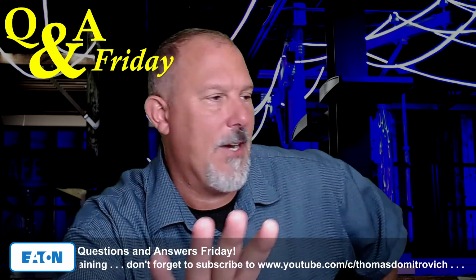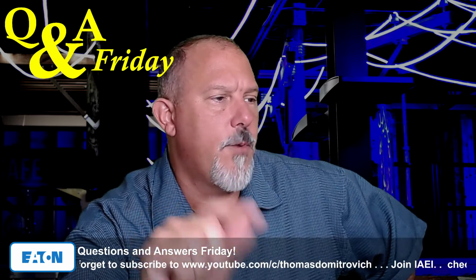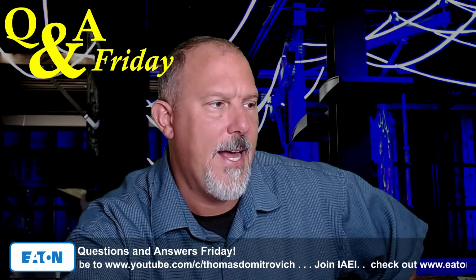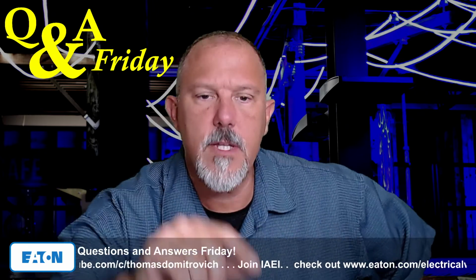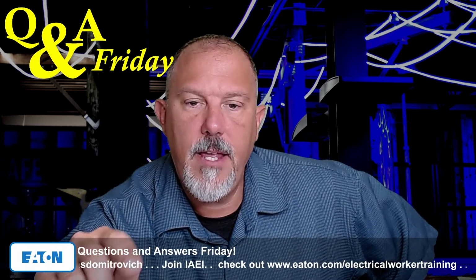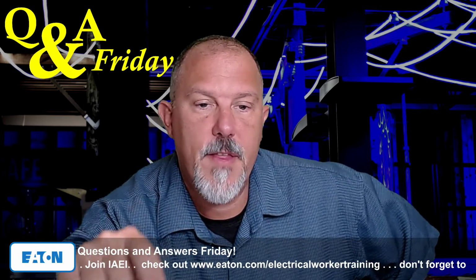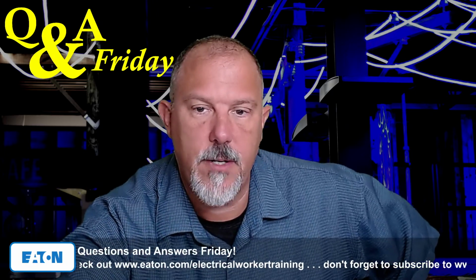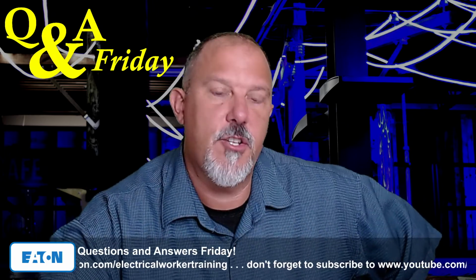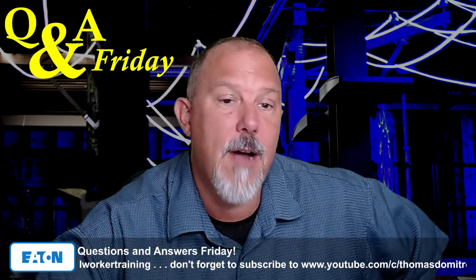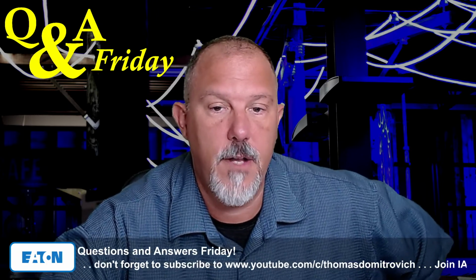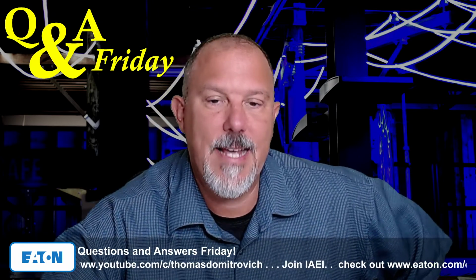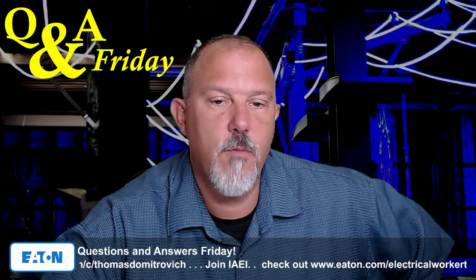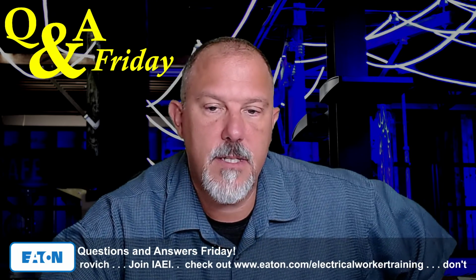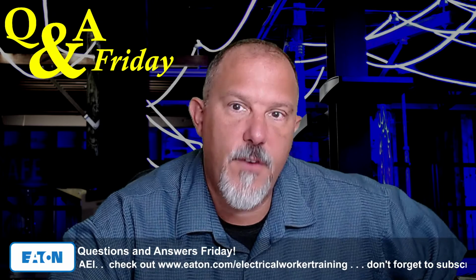Wait a second. Okay, well, I'm going to read this entirely. I have a question. Suppose we have grid supply with 500 MVA, assume an infinite bus. Now, if I connect an isolation transformer of small kVA of equal turns ratio from the grid, consider a 4000 kVA transformer. Now I calculate transformer secondary current and then fault current by dividing it by the transformer impedance. So if a fault occurs on the transformer primary terminal, how much higher fault current should flow than if a fault occurs on the secondary terminal? How is an isolation transformer able to reduce fault current? Does the transformer saturate? I know the transformer has impedance, but would that impedance be able to limit fault current that much?